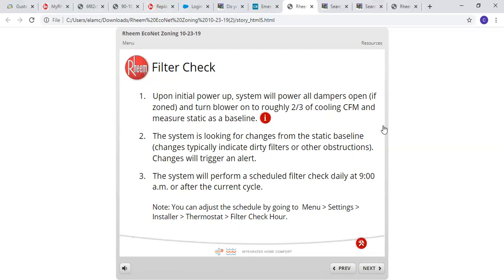Down the road, once it's installed and set up, if there's any kind of major change, you're going to get a replace filter alert. The system will perform a scheduled filter check every day at 9 a.m. So every day at 9 a.m., it's going to start up and do its quick filter check, and if it detects a problem, it's going to trigger an alert. You can adjust the schedule by going into the menu, settings, installer, thermostat, and then you can change the filter check hour time.